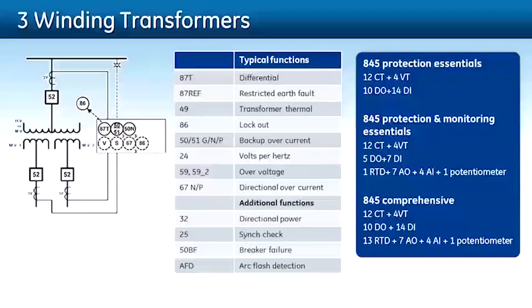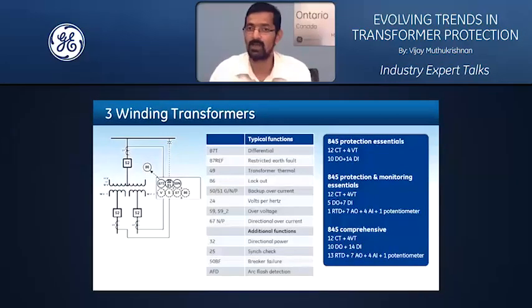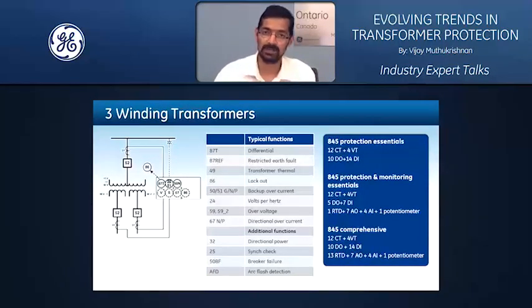The next, two-winding applications we saw. The same way, when you have a need for a three-winding transformer application, the way you really look at it is that your transformer protection relay should be able to process three-winding input currents, do the phase and magnitude compensations, and do the differential protection with the three-winding currents coming into the protection relay, able to support you up to 3 restricted ground fault elements if you need in your application, and on top of that add all the voltage based protections, the integrated arc flash, those type of scenarios. So this is the comprehensive approach when you have a three-winding transformer.